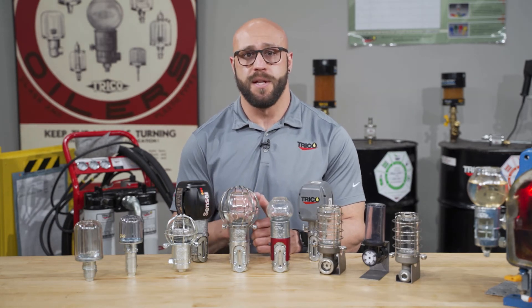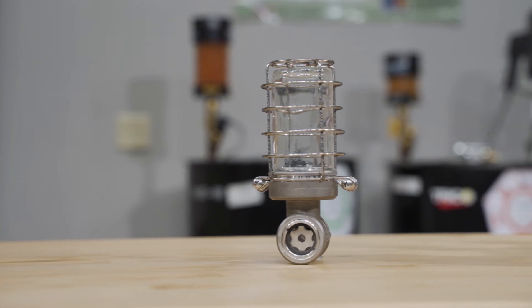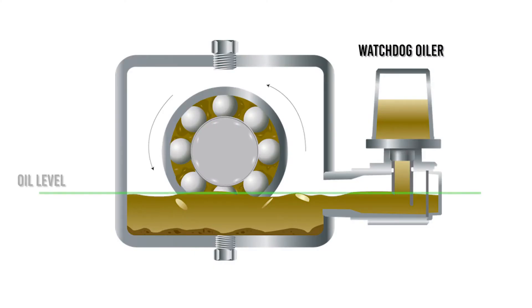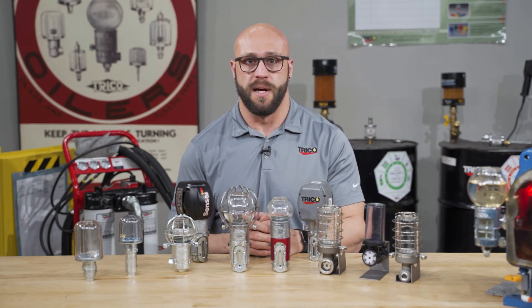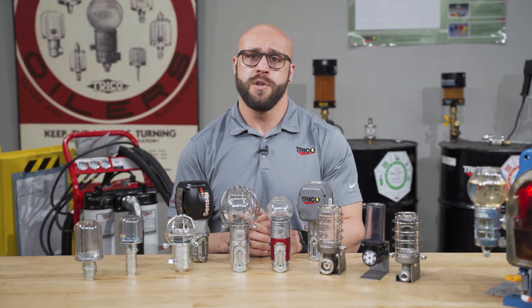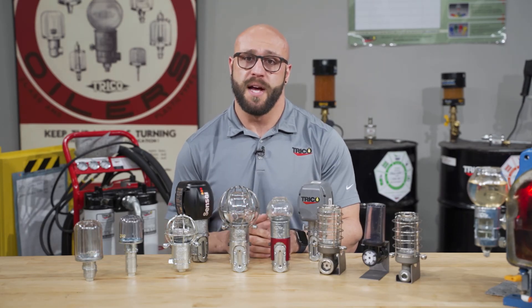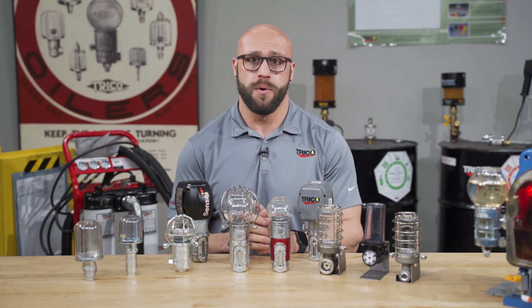Proper air exchange can then be achieved by installing a pressure balancing line to your equipment. The last of the constant level oilers is our watchdog oiler. Almost immediately after releasing the closed system oiler, Trico introduced the watchdog oiler. This product was an answer to the industry wanting a non-adjustable oiler. The watchdog was designed to be installed on the centerline port of the oil sump level, where you would typically see a bullseye sight glass. The reservoir is threaded down and stops at the control point that is even with the centerline of your oil level — therefore, no adjustment is required. The watchdog is also considered a closed system oiler, as it shares the head space with the oil sump, removing any need for it to exchange air with the surrounding environment. The watchdog oiler is available in a metal and glass construction or in an engineered thermoplastic version called polysulfone. The thermoplastic version is only available in a one-inch NPT configuration, while the metal versions allow for a one-inch, three-quarter, or half-inch NPT.